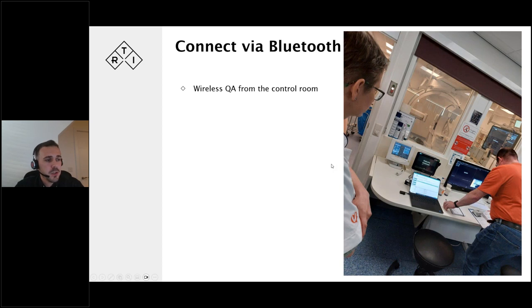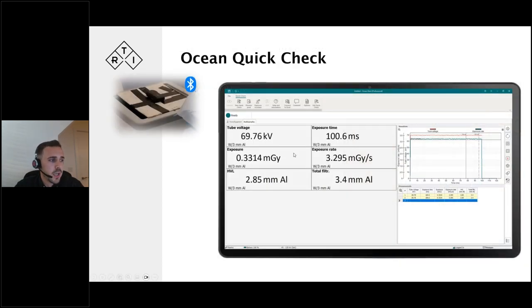Sometimes if you just walk up to the system and want to make a simple measurement, just check the KV or the dose output of the system, that's where you use the first step, which is QuickCheck. In QuickCheck, we have a very simple display of the measurement parameters.